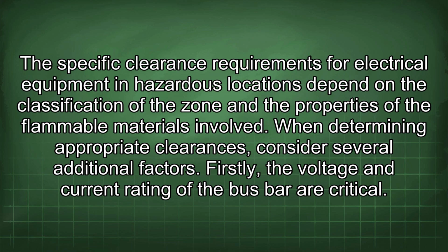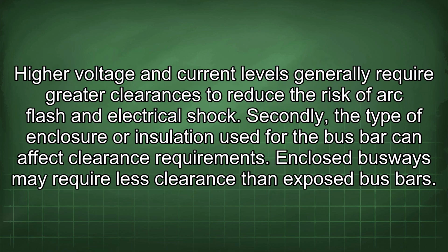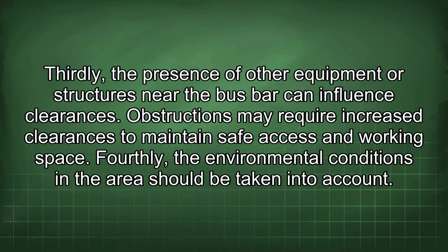When determining appropriate clearances, consider several additional factors. Firstly, the voltage and current rating of the bus bar are critical. Higher voltage and current levels generally require greater clearances to reduce the risk of arc flash and electrical shock. Secondly, the type of enclosure or insulation used for the bus bar can affect clearance requirements. Enclosed busways may require less clearance than exposed bus bars. Thirdly, the presence of other equipment or structures near the bus bar can influence clearances. Obstructions may require increased clearances to maintain safe access and working space.